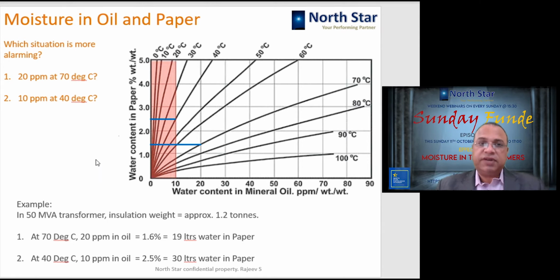So a transformer which is working at 60 degrees centigrade, if it is having a ppm around 3 to 4 ppm, then you can say your paper is dry, that is having the moisture around 0.5, 0.6%. Of course, all this information is based on some experiment done in some particular condition. So as such, these conclusions cannot be applied, but it is giving us an idea of where to look and what to look for. Okay, so I hope this information is useful to you.